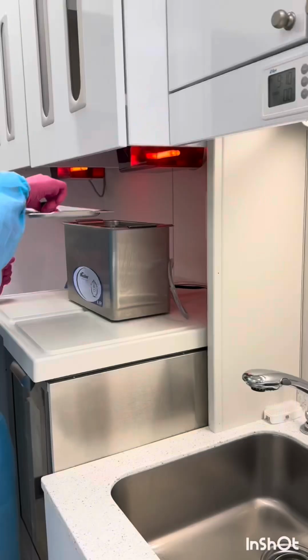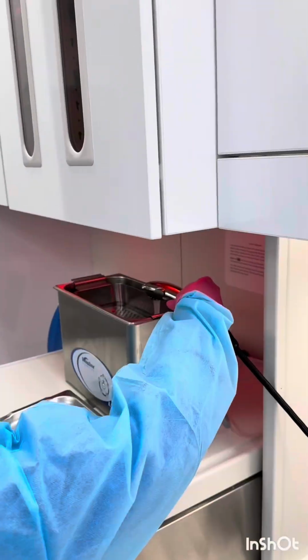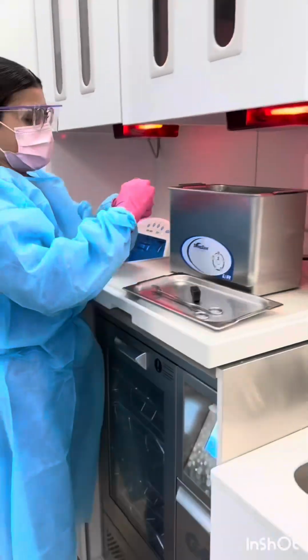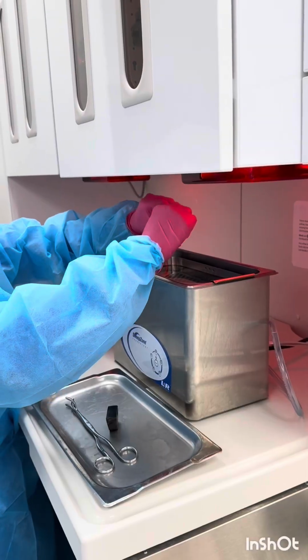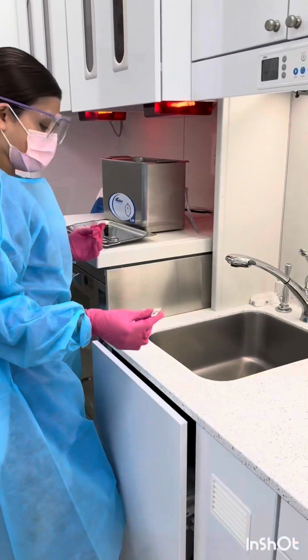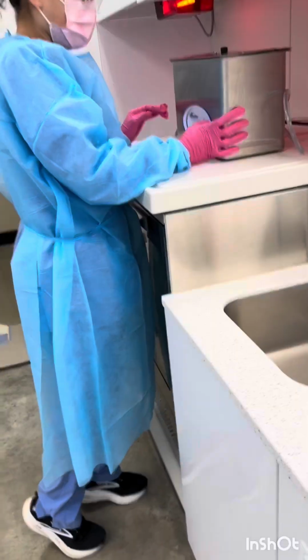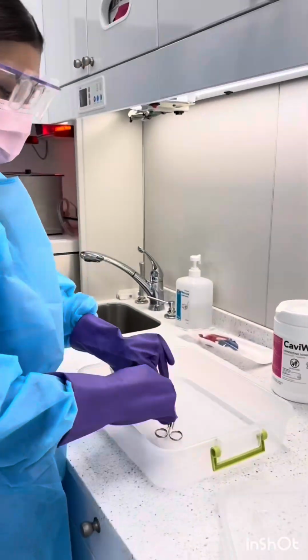Loose instruments are placed in the ultrasonic cleaner, which is also used to remove debris and biofilm. This machine runs for about 6 minutes. The ultrasonic should be filled and emptied every single day. We place a cleaning tablet at the beginning of each day, and we run it with that one load to assure the tablet has dissolved.